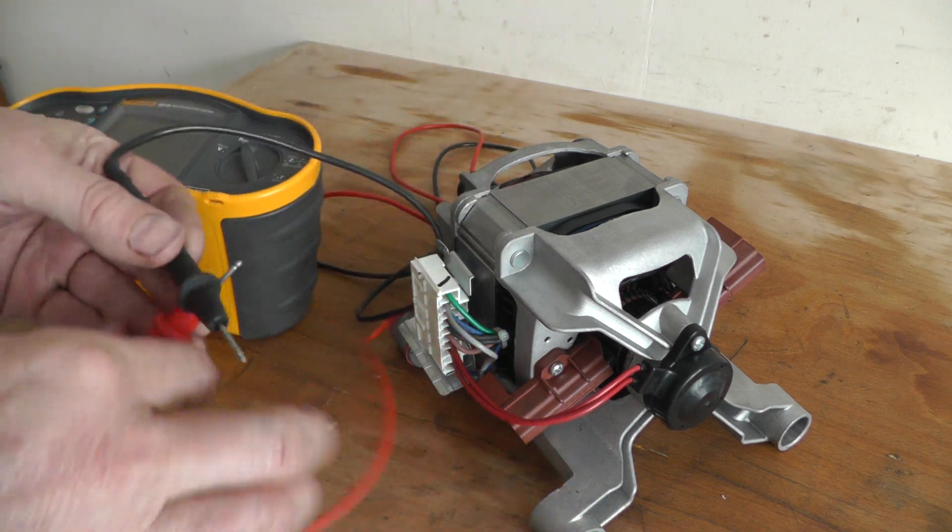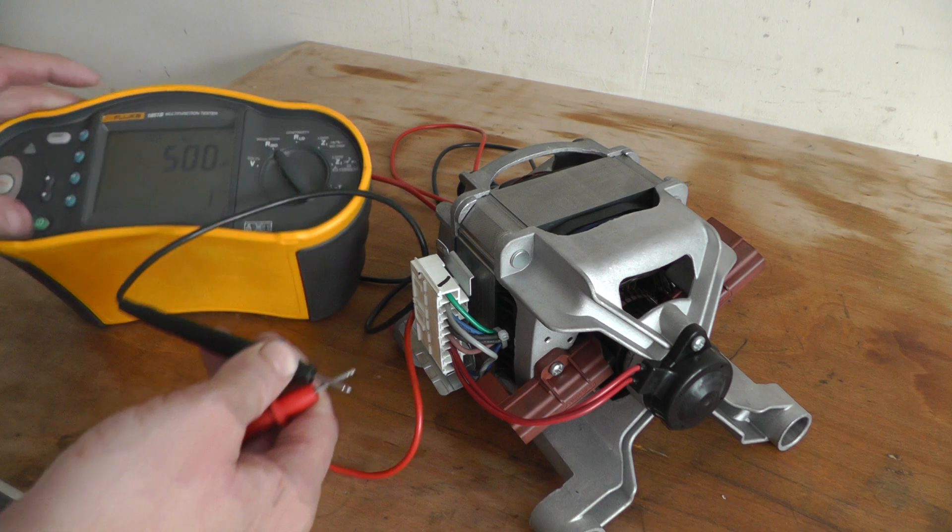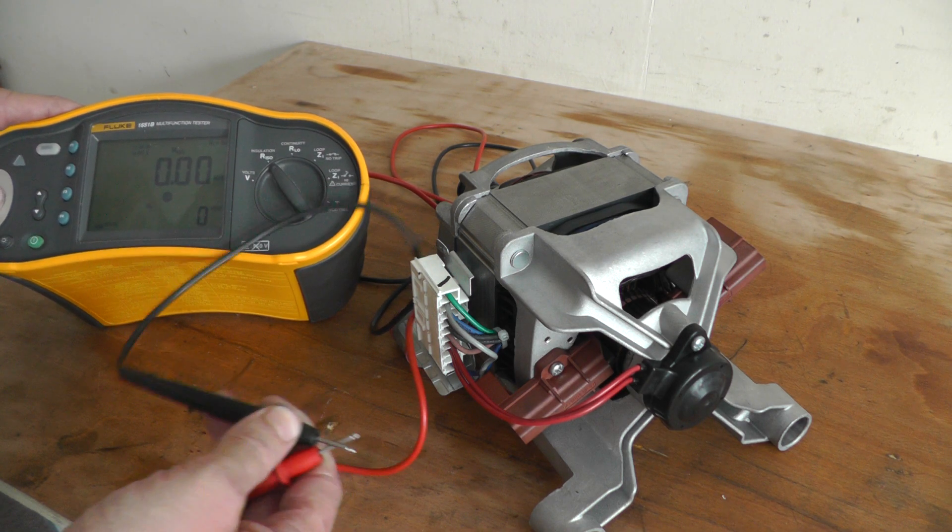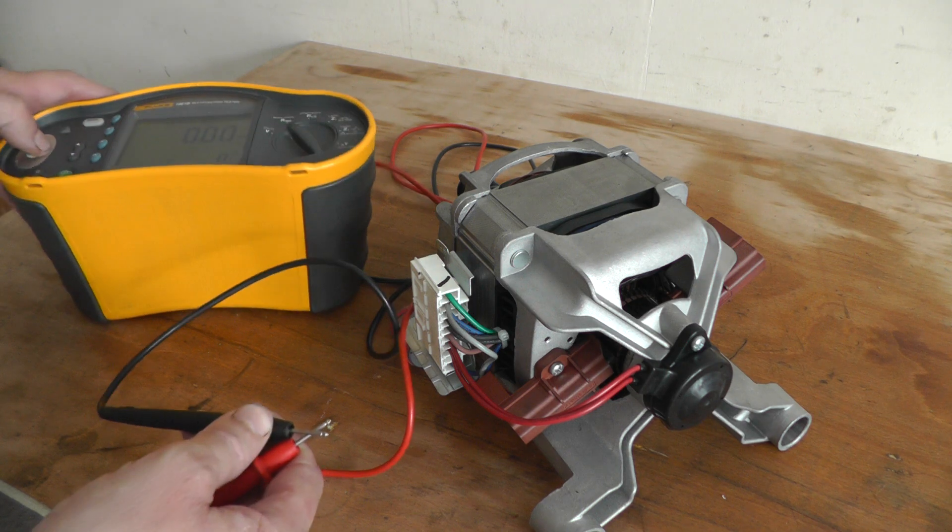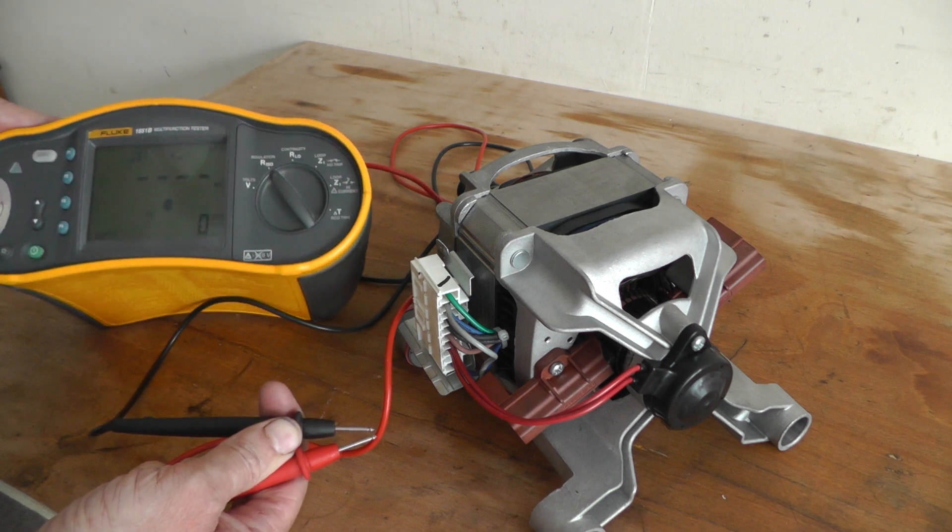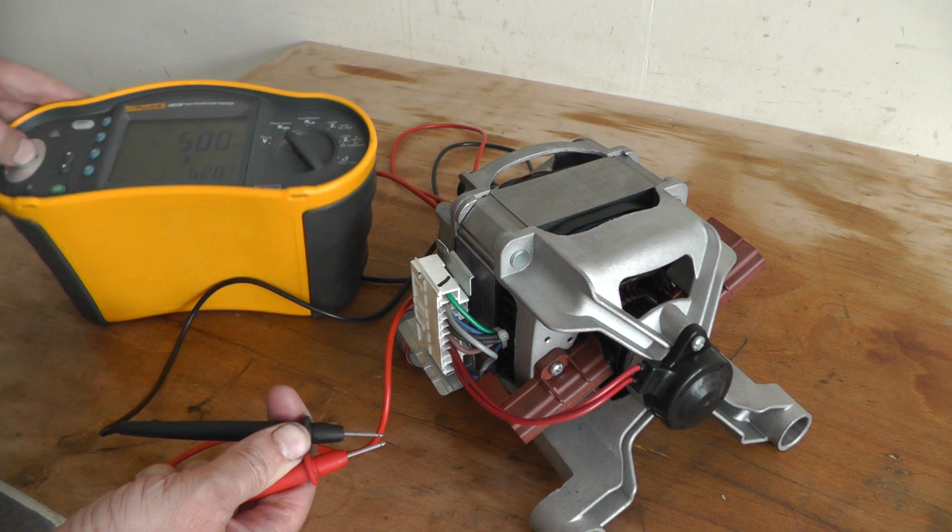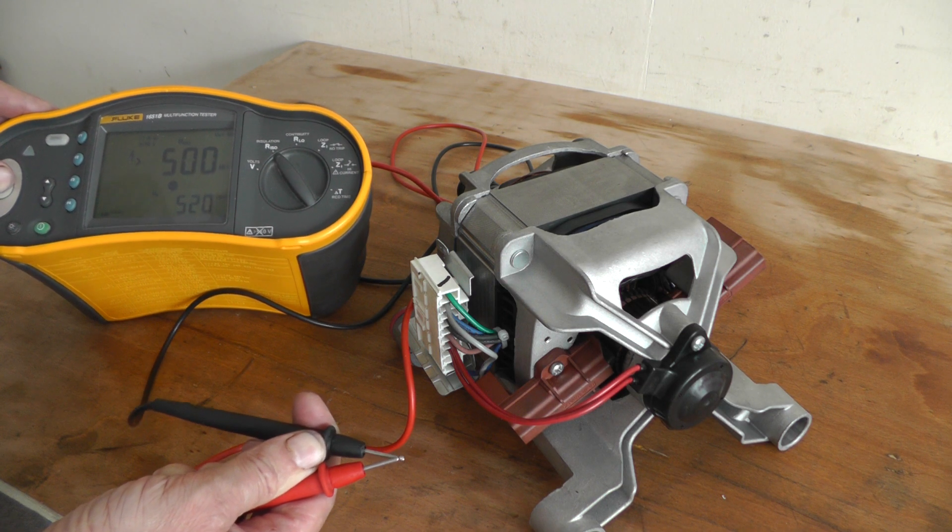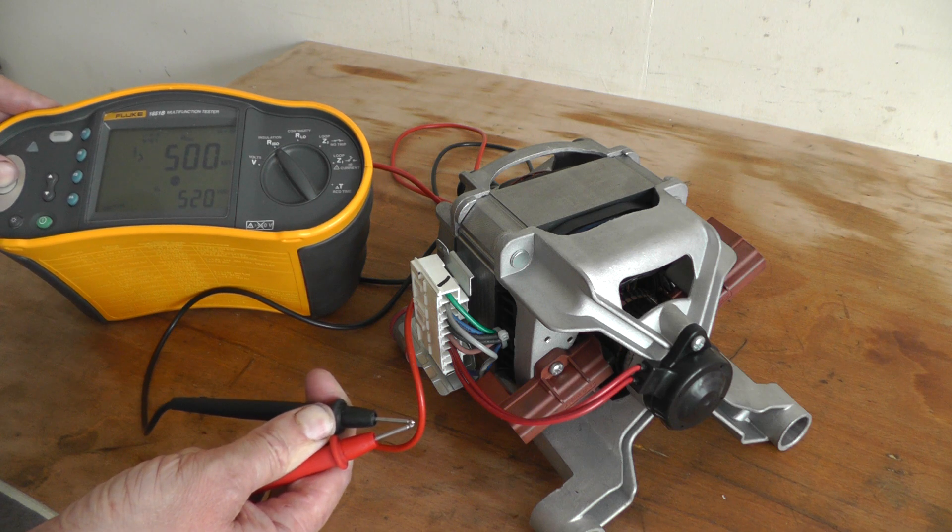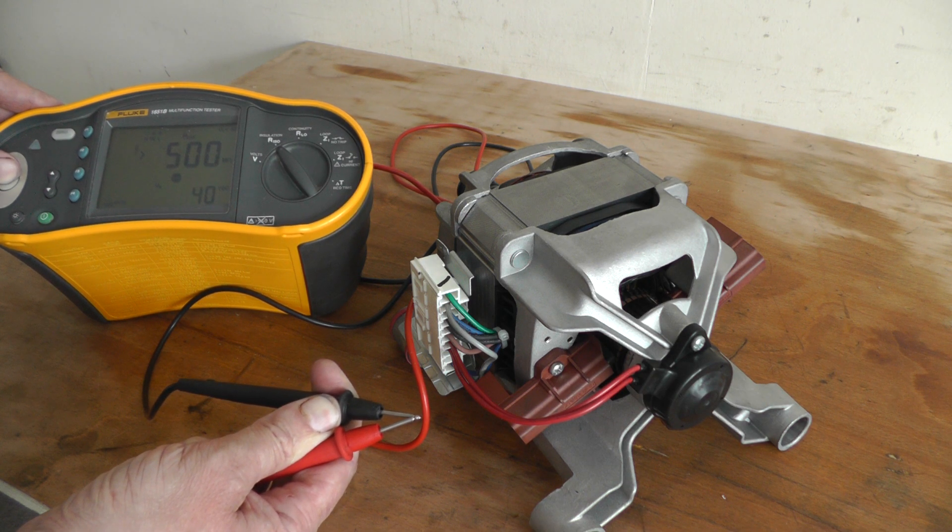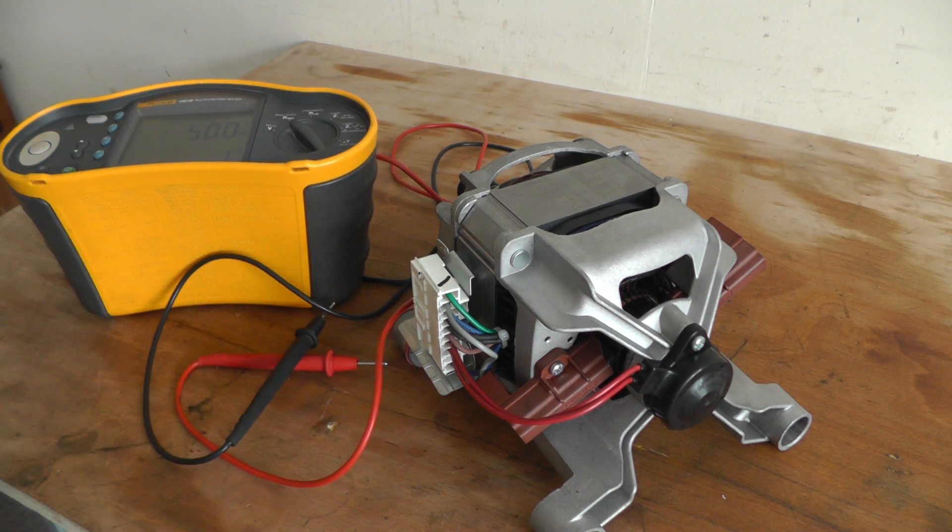I'll just short them leads out though and show you what a really bad short circuit would look like. Obviously you get no insulation resistance. I'll put them really close together. Still greater than 500. And well, that's how you test your motor anyway, alright.